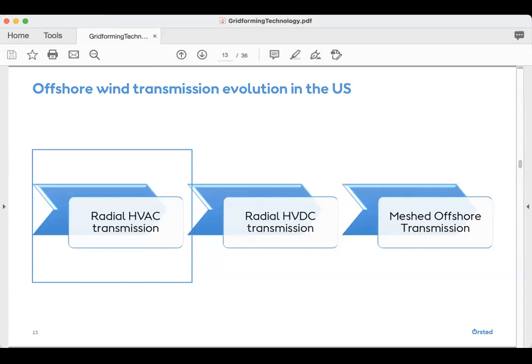So on the offshore end, where you have no synchronous machine, the HVDC VSC technology provides the grid forming ability that one would need to operate the wind turbines today, and we'll discuss that once we get to that section.